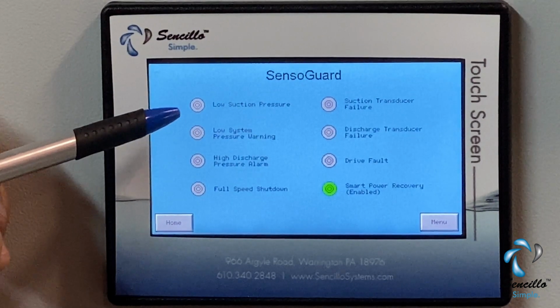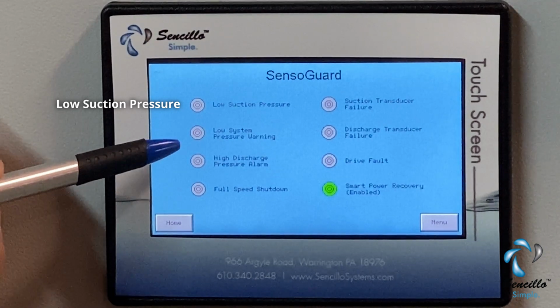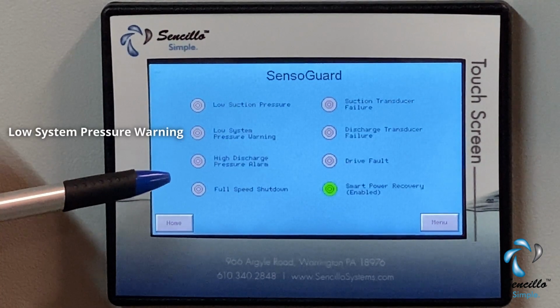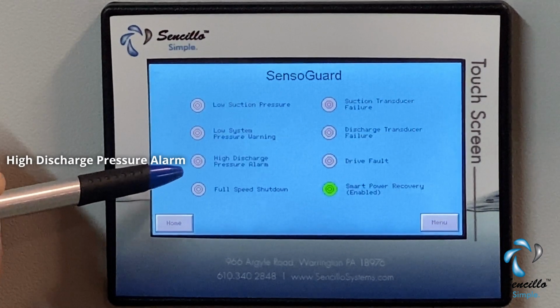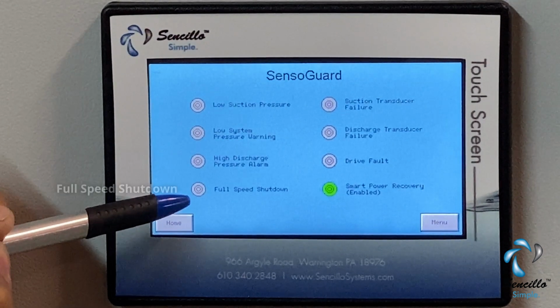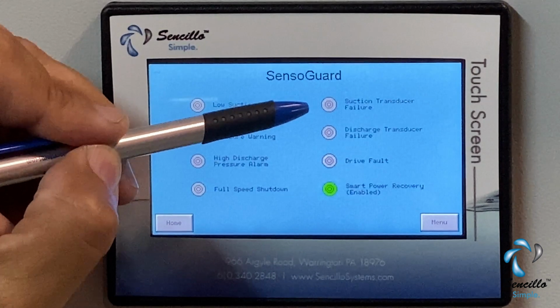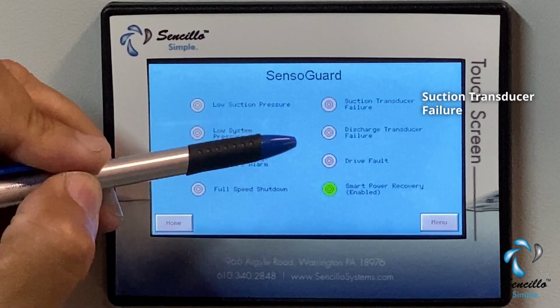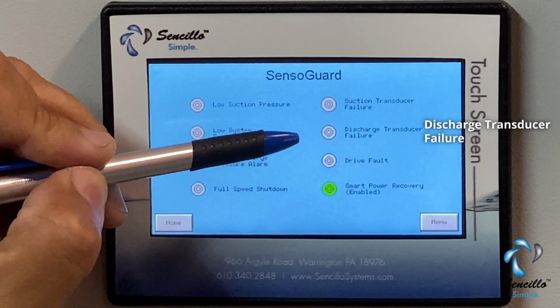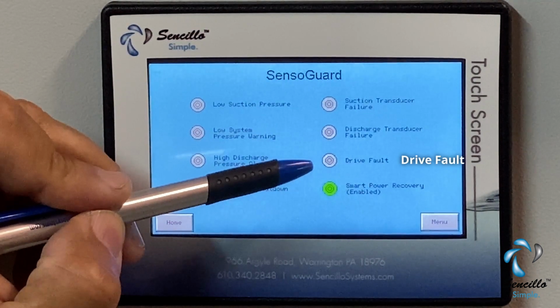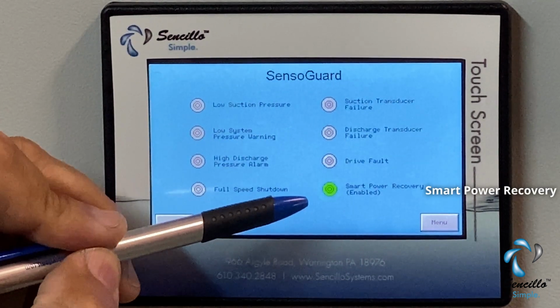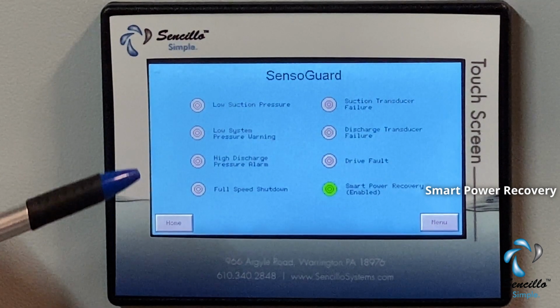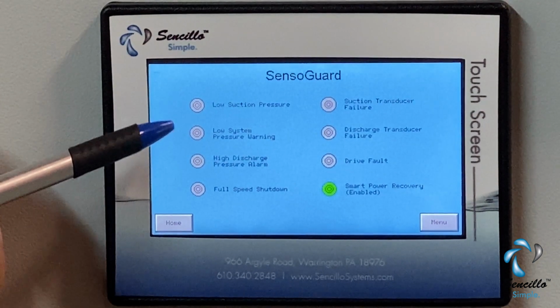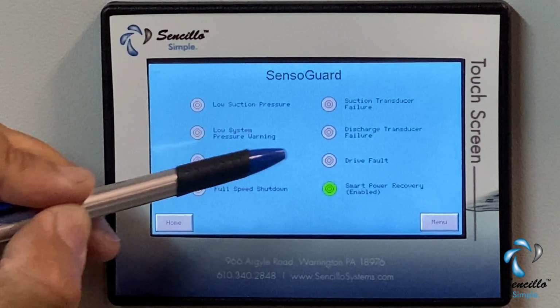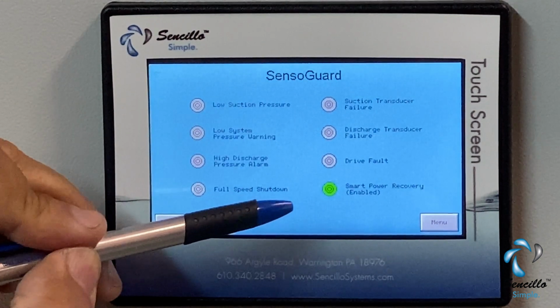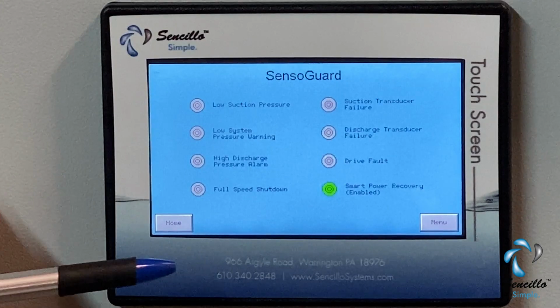We have a low suction pressure, low system pressure warning, high discharge pressure alarm, full speed shutdown, suction transducer failure, discharge transducer failure, drive fault, and smart power recovery. When you do have an alarm, these indicators will turn red. The smart power recovery is green because it is now enabled.